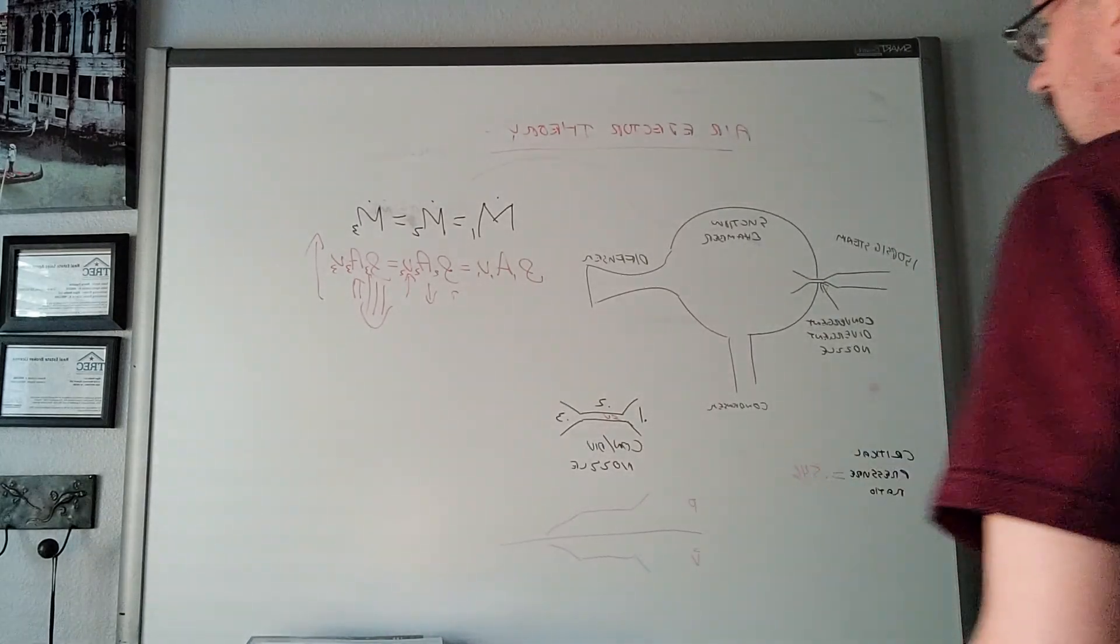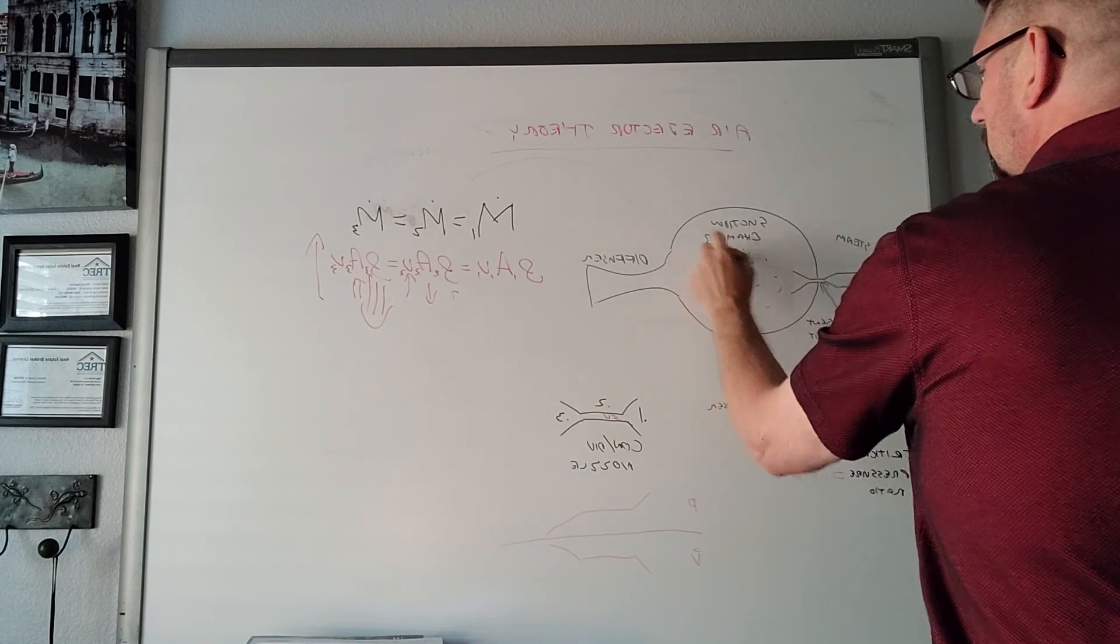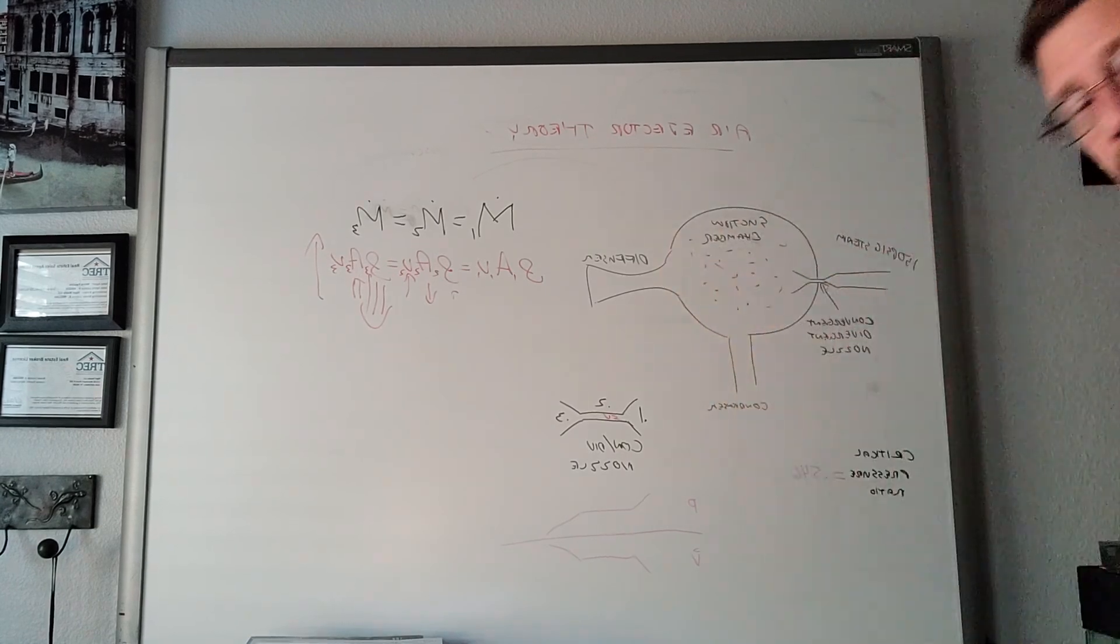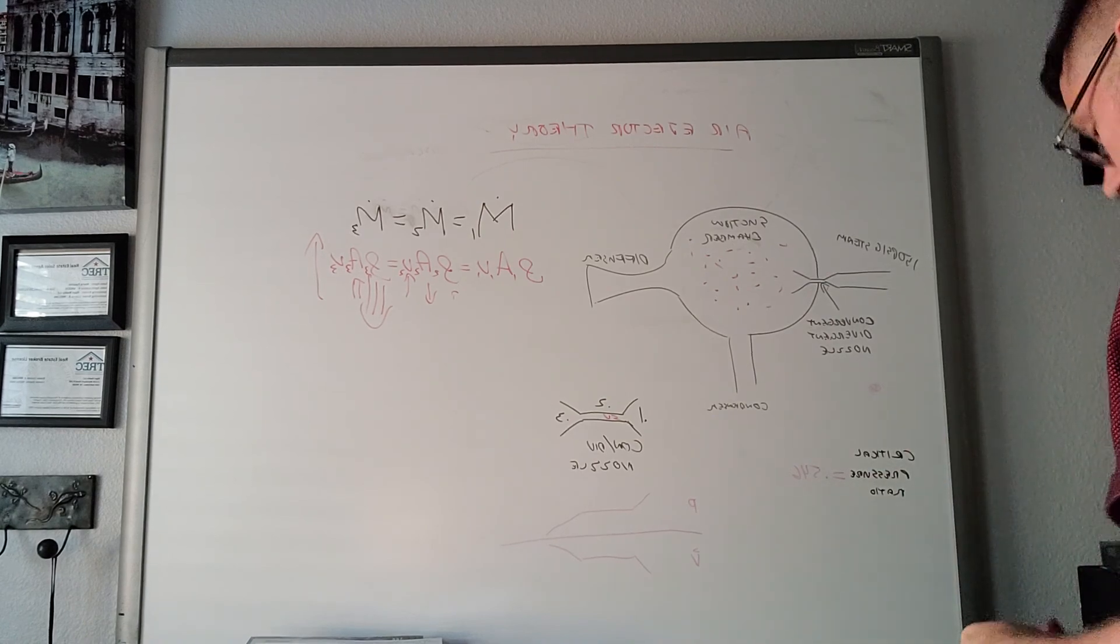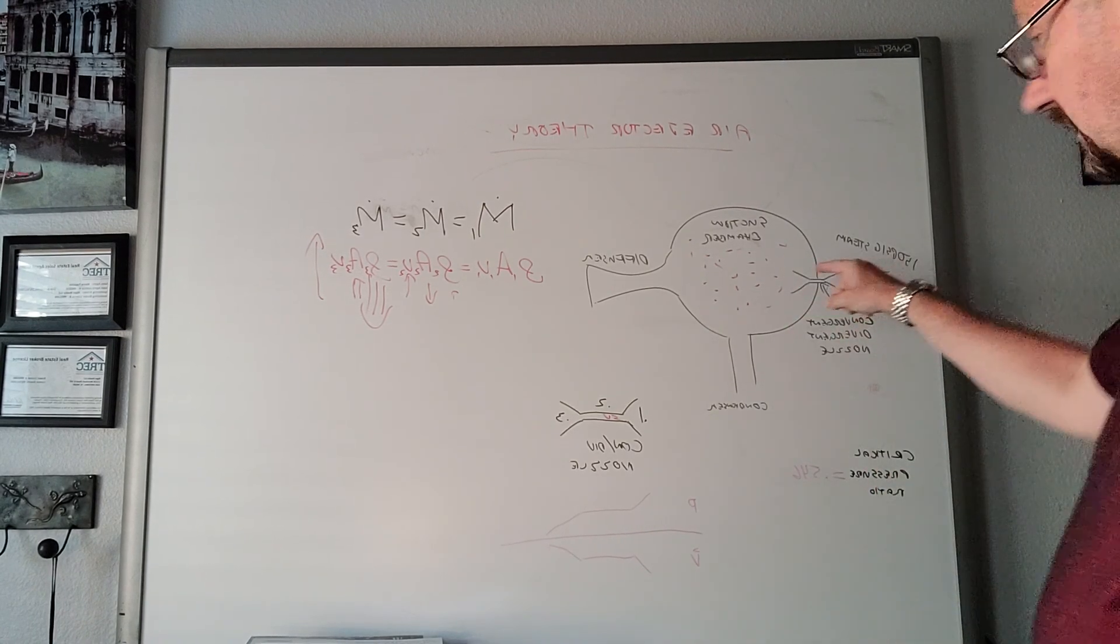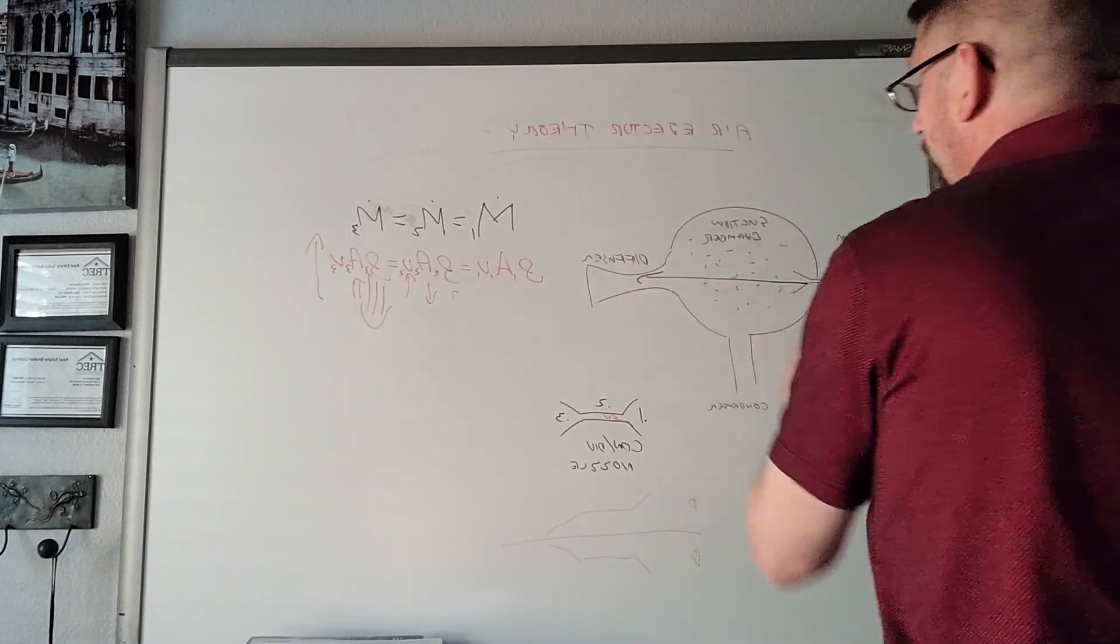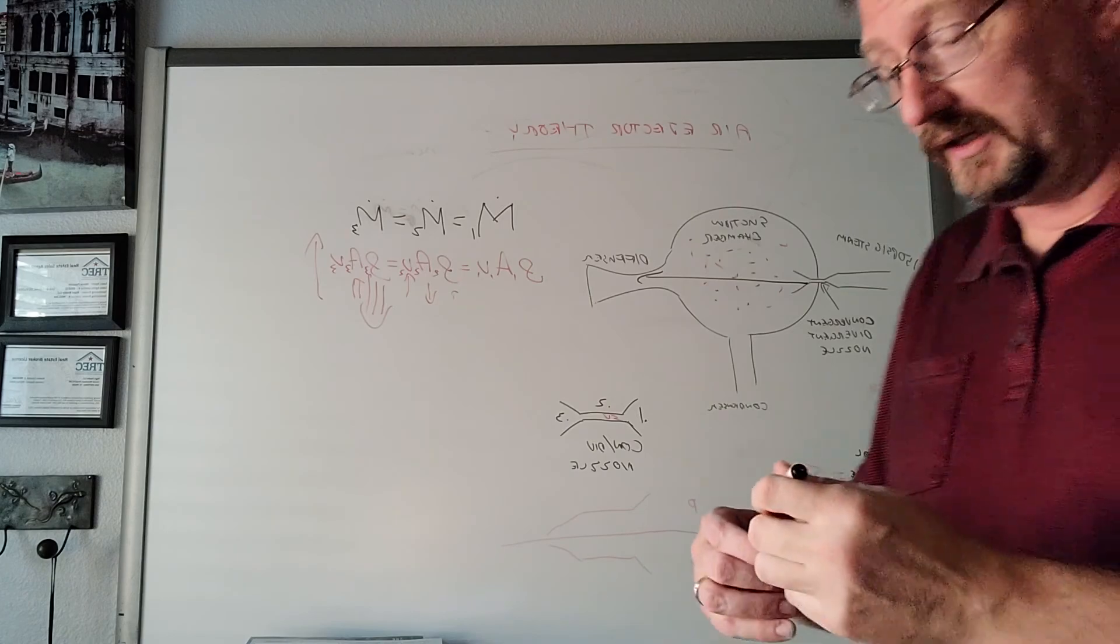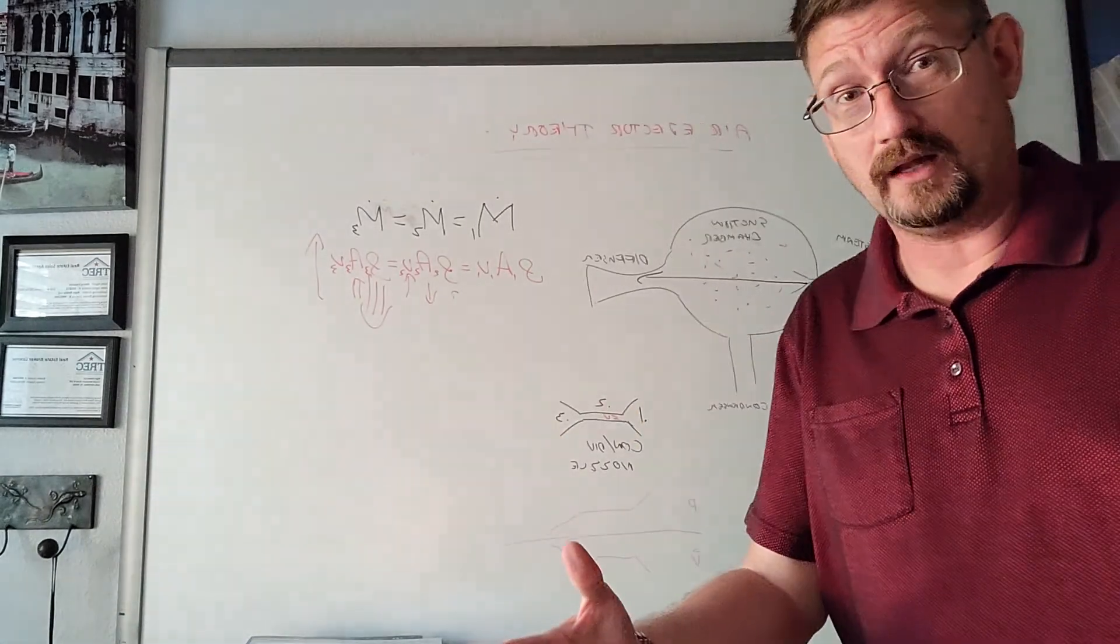Inside the suction chamber, I've got all kinds of air and non-condensable gases. I'm going to take that supersonic steam and send it flying through here, and it's going to molecularly entrain the air and non-condensable gases one molecule at a time. What does molecularly entrain mean?